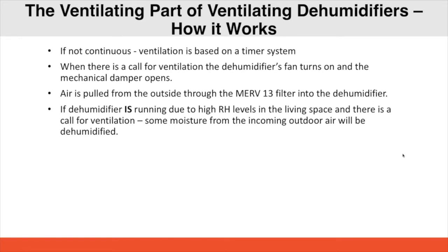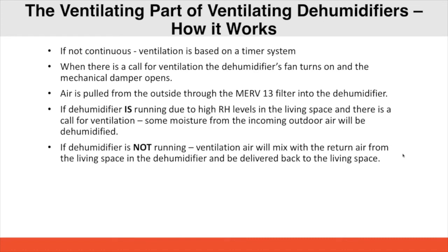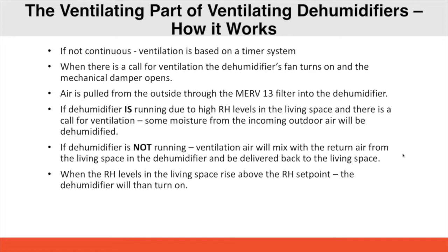If the dehumidifier is running, which means the compressor of the dehumidifier is on due to high relative humidity levels in the living space, and there's a call for ventilation, then some moisture from the incoming outdoor air will be dehumidified. If the dehumidifier is not running, meaning the compressor is not running, the ventilation air will mix with the return air from the living space and the dehumidifier and then be delivered to the living space. So when the RH levels in the living space rise above the relative humidity set point, the dehumidifier will turn on.